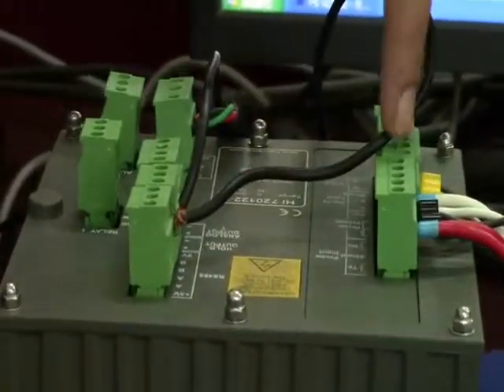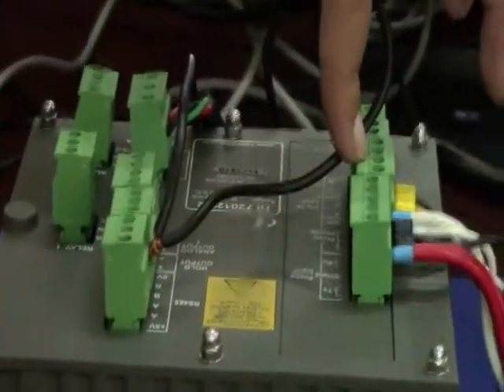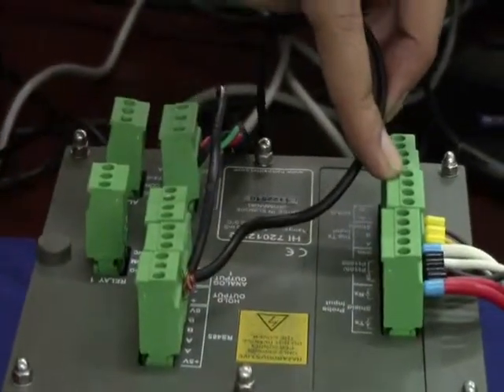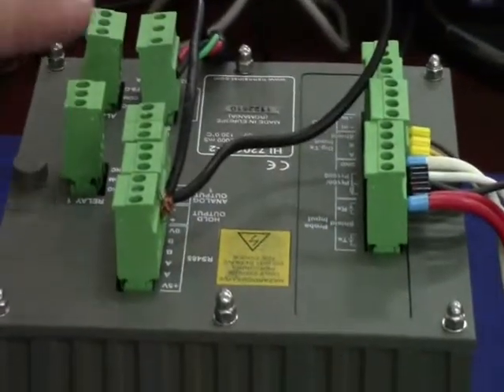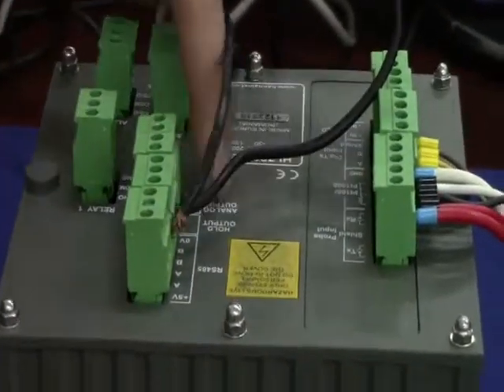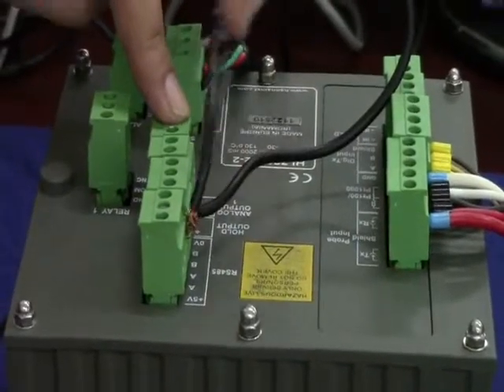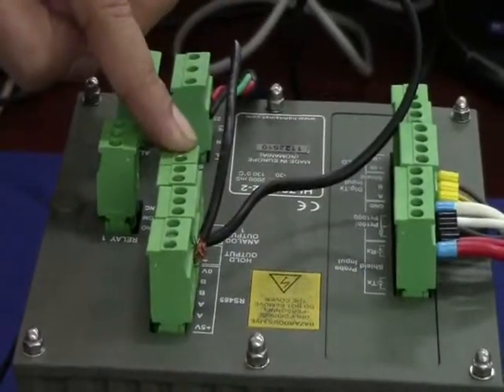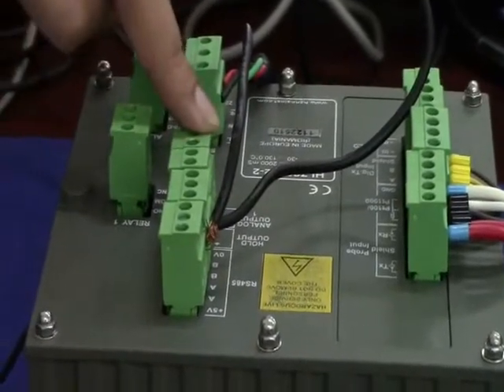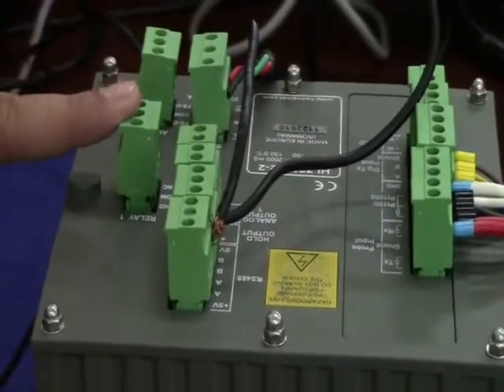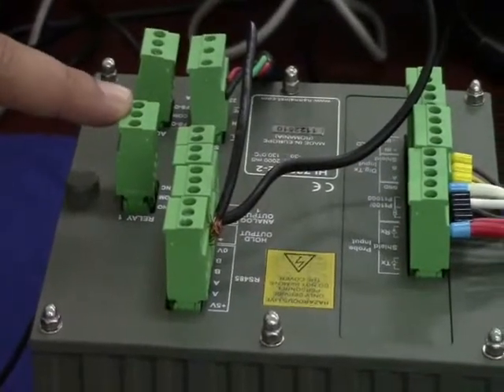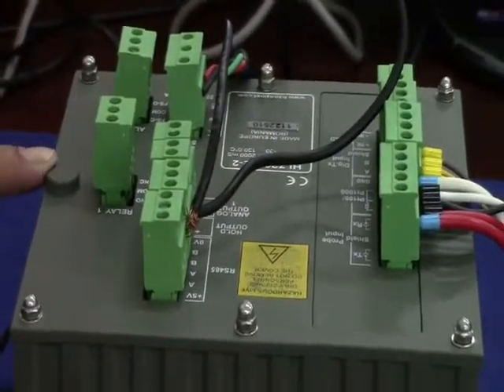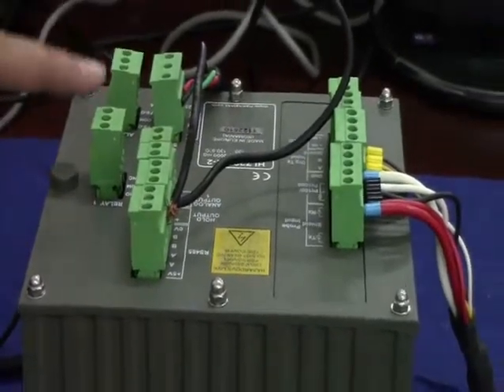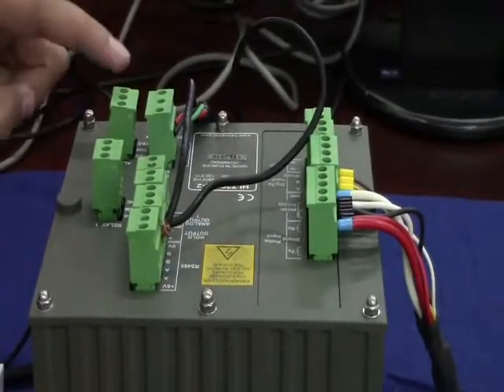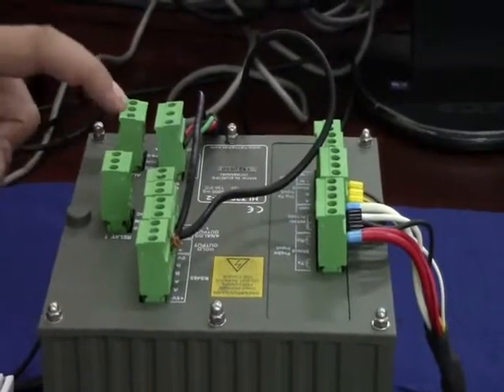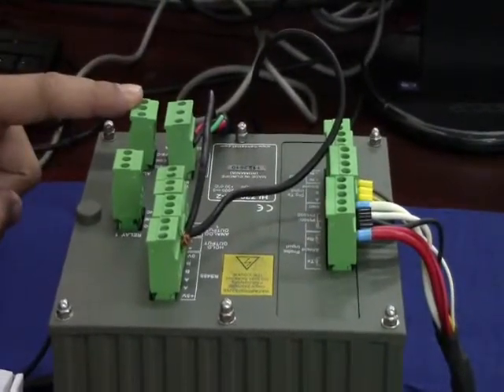As you can see, the probe has already been connected with the inbuilt temperature sensor connections. Now, the customer can use the analog output 1 port for connecting it with a recorder or any device of an analog signal. Relay 1 is connected to set point 1. The customer can connect a dosing pump or an actuated control valve to control the set point. This is an alarm relay which the customer can use to connect to a buzzer or an alarm device.